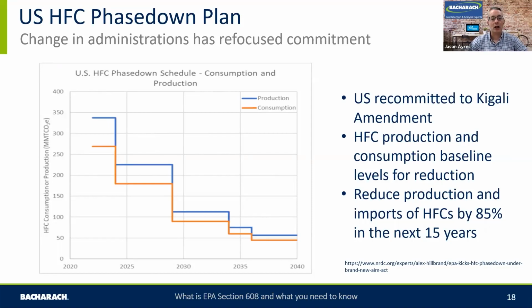So it's not about the physical amount of refrigerant, it's that amount of refrigerant and its CO2 equivalent. So it's guiding consumers, equipment manufacturers, and people who are potentially going to buy refrigerant to use lower GWP alternatives. Again, that could still be an HFC, or it could move you to HFOs or natural refrigerants. And this is a 15-year program, so it gives time for the industry to recognise and to plan for those transitions. There is a step down. They come down in step downs. For the first 2 years, the production level is looking only at a 10% reduction on whatever baseline is going to be agreed.